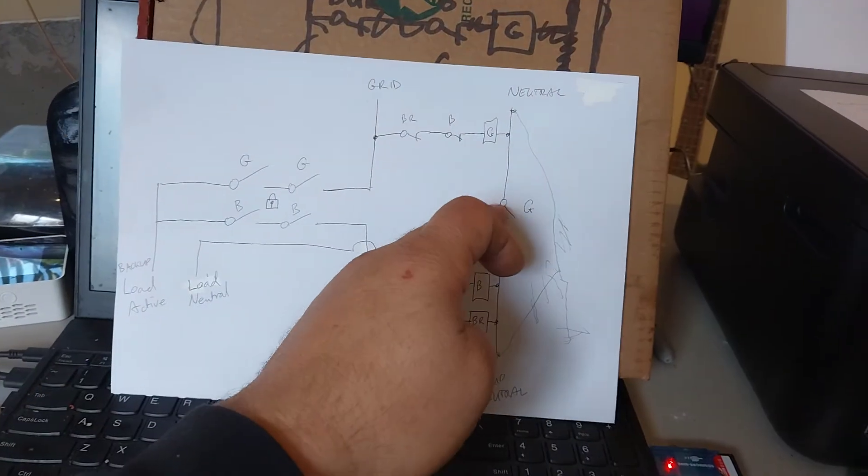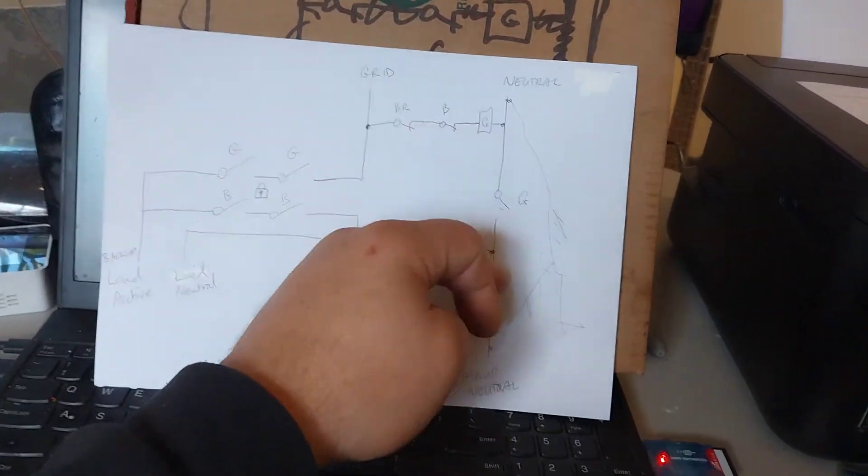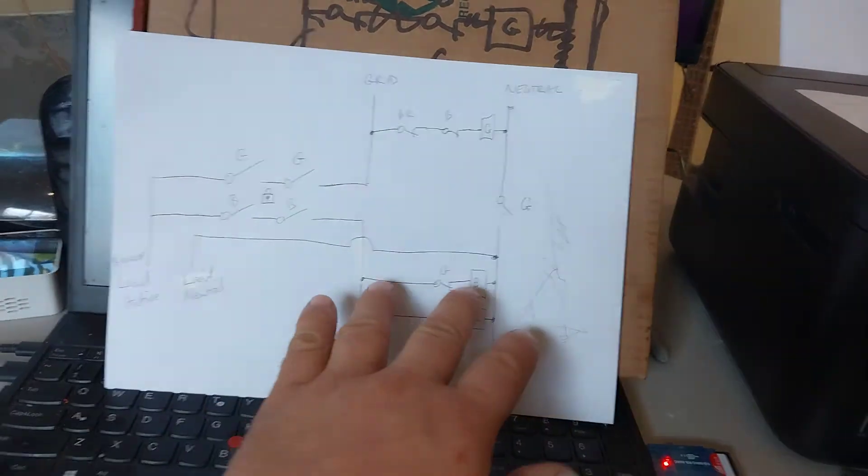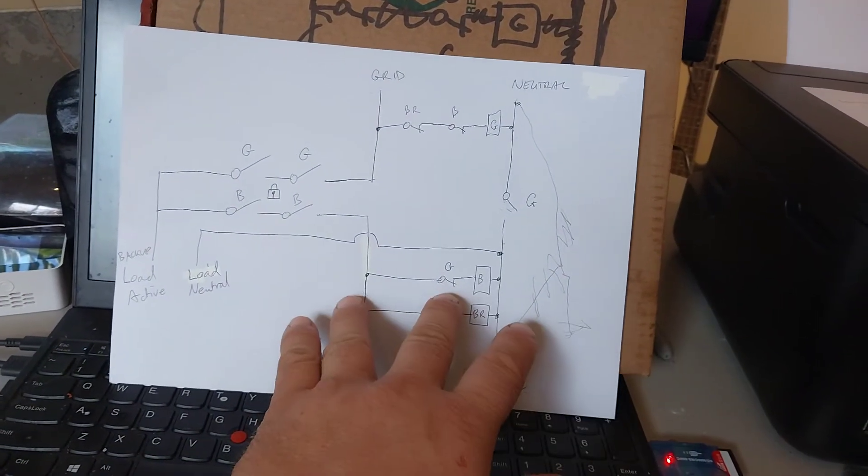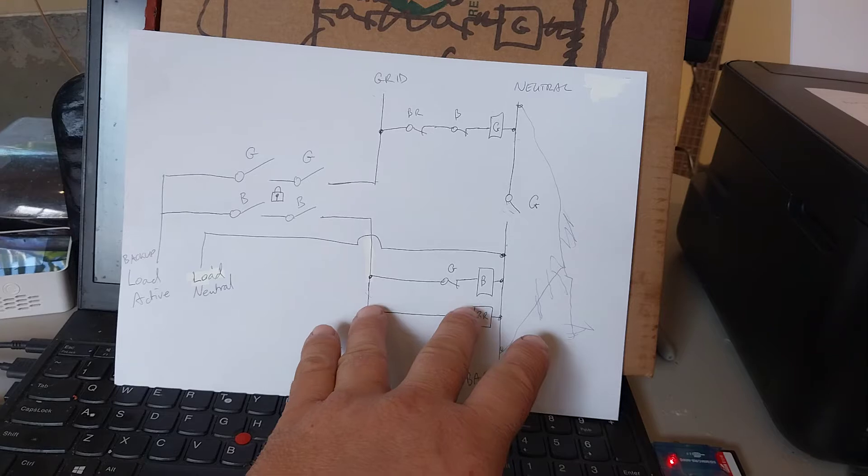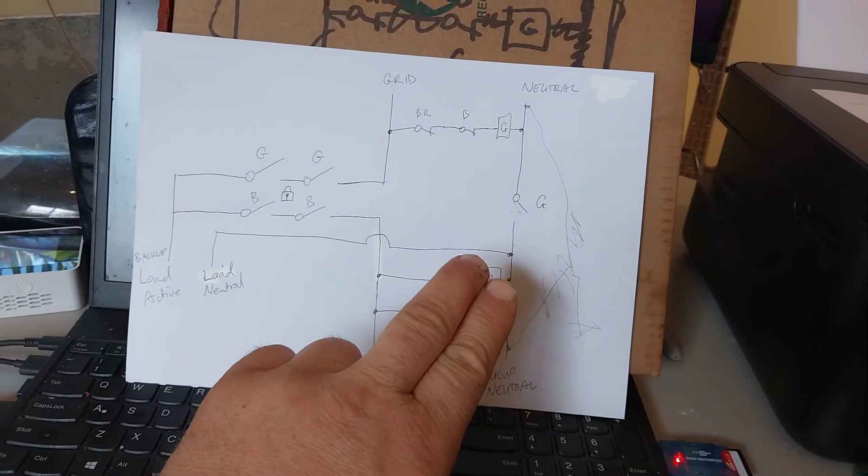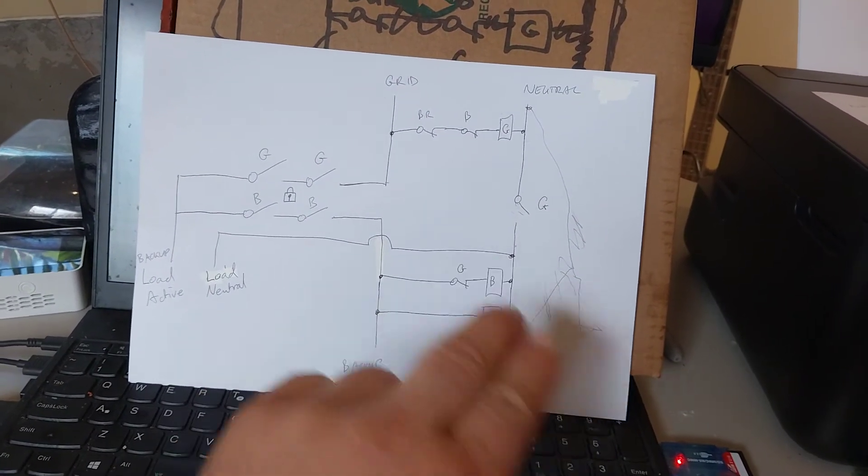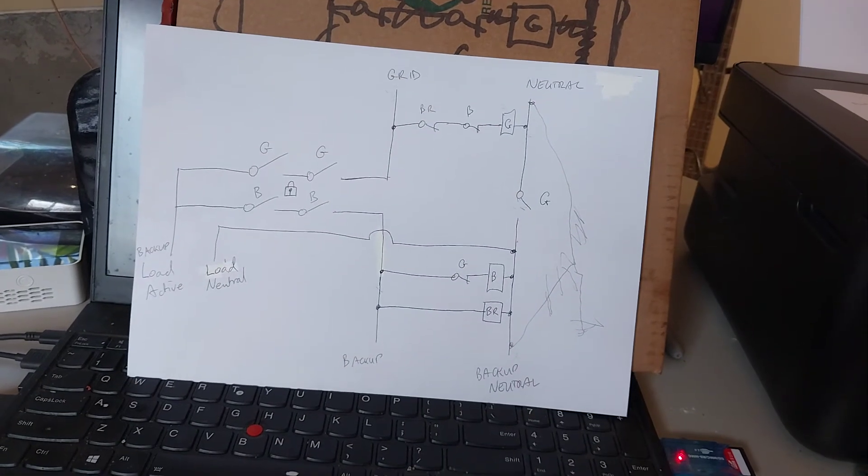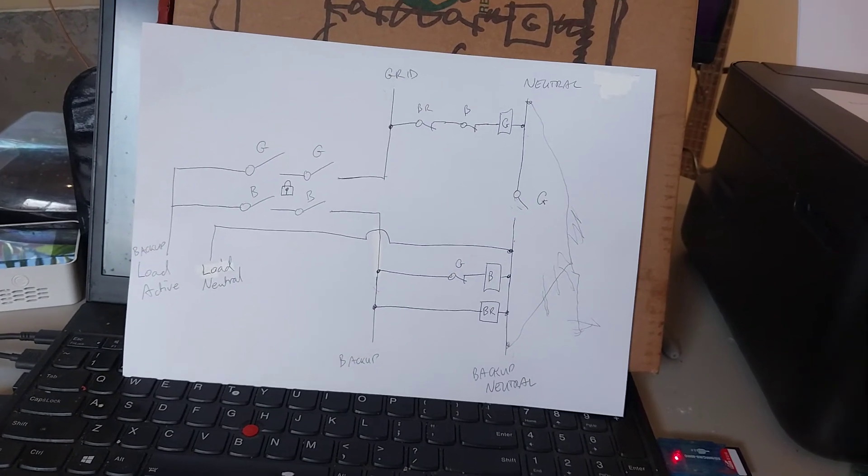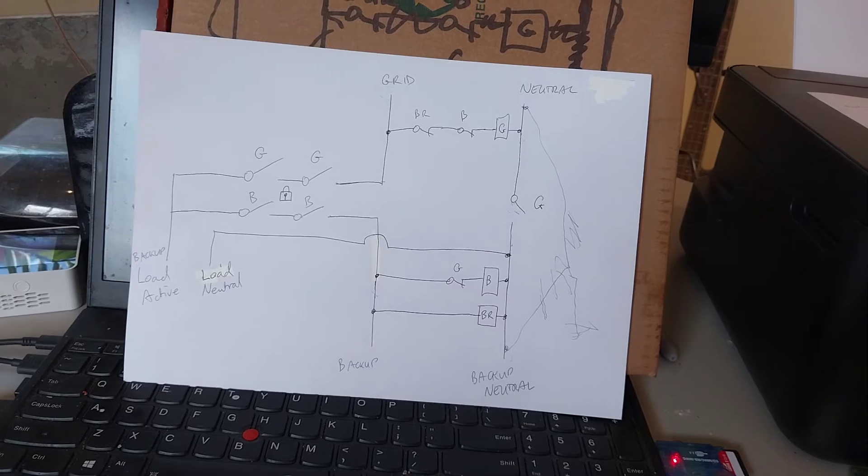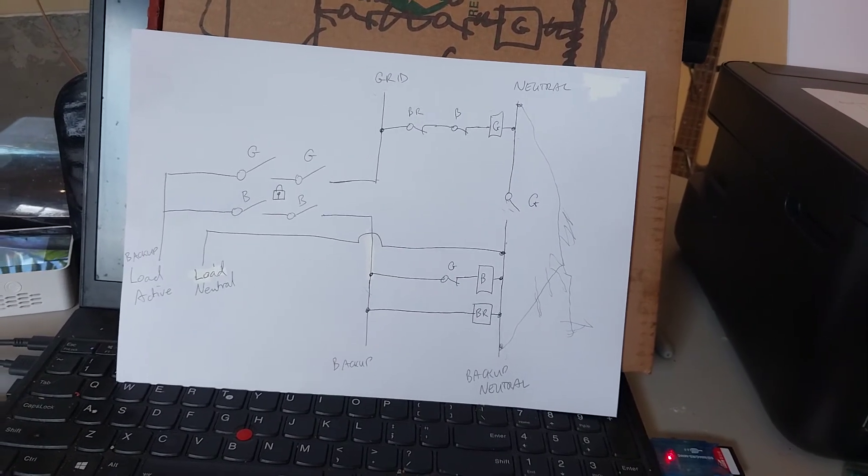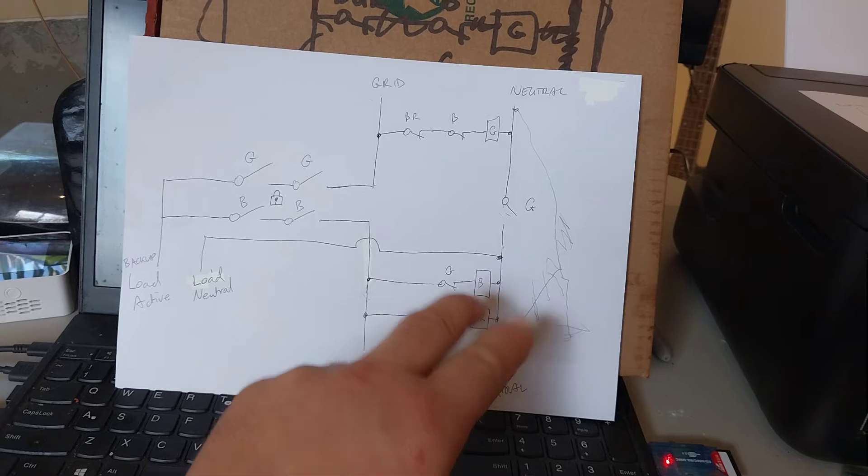Regarding this separation of the two neutrals, it's mainly because when there's no grid and the Solus inverter is in backup mode, it will close contacts in the inverter between the neutral and the earth to make what's called a multiple earth neutral. That allows your safety switches to trip. Your 30 milliamp, in Australia anyway, 30 milliamp safety switches to trip and it closes it there.